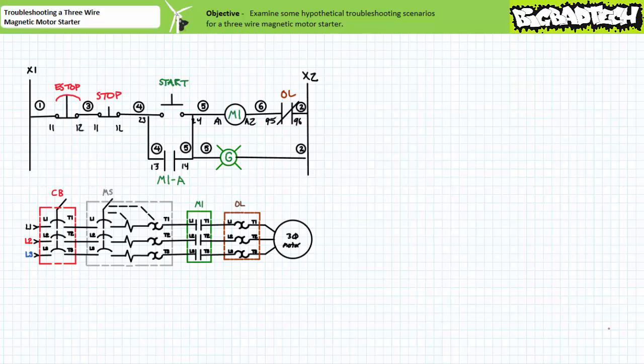You should realize that this circuit exhibits certain expected behaviors that although potentially undesirable are not to be considered troubleshooting events, but are rather byproducts of the as-constructed nature of this circuit. A technician knowledgeable of basic technical principles and the circuit's intended function can predict this behavior and take the necessary precautions. Note the control transformer wired between the circuit breaker and the manual motor starter is not expressly illustrated in this primary circuit. With this consideration, consider the response of this system to a sudden loss and restoration of power or an overload event.